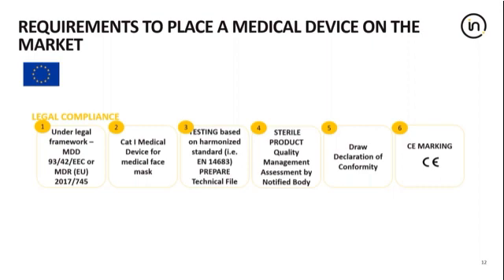And it should include all relevant design, material, labels, packaging, and other relevant information in the technical file. And it could include things such as the bill of materials to show a consistency in production and performance, design drawings, and this may include details of the filtration medium, for example, label files, and the technical file should contain details of the labeling which should be applied to the product, packaging files, which includes the packaging specification to ensure the integrity of the product, details of the applied standards, which would usually be EN 14683, the test reports for the testing program, any QC reports, which would be used for control during production, and any risk assessment which has been carried out.